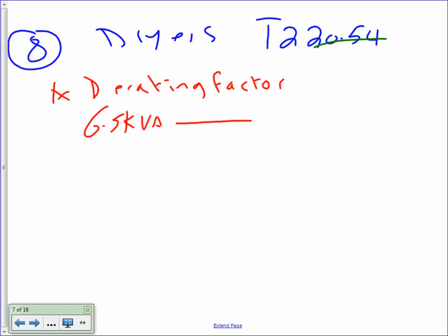You're going to take this to table 220.54 for 30 of them. Remember, there's 30 of them. You're going to get the following. There's a couple of calculations that you have to do here. Let's go do the calculation. The calculation goes as this.